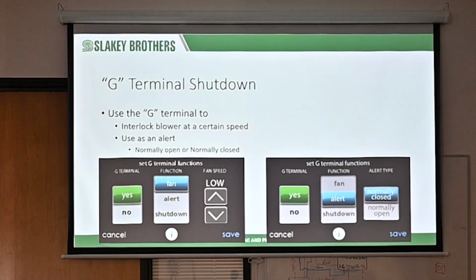Okay, G terminal shutdown. You guys ever install condensate pumps? Yep. Condensate pumps have a little safety switch. It's really easy on a regular furnace. You just break the R terminal, and that's how you set the safety switch. On the Connex, it's different. We don't want to shut anything down. We don't want to force error codes to happen that don't need to happen, but we want to know if the condensate pump isn't working.